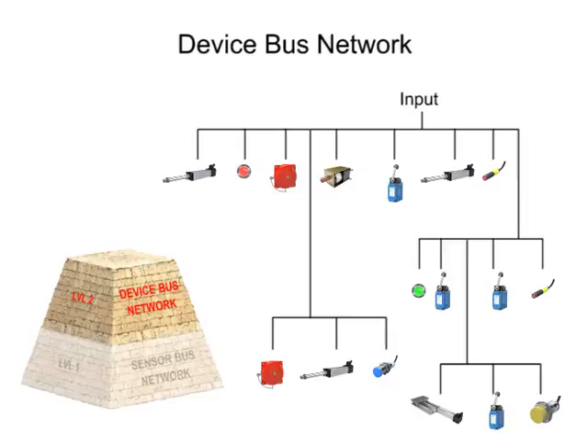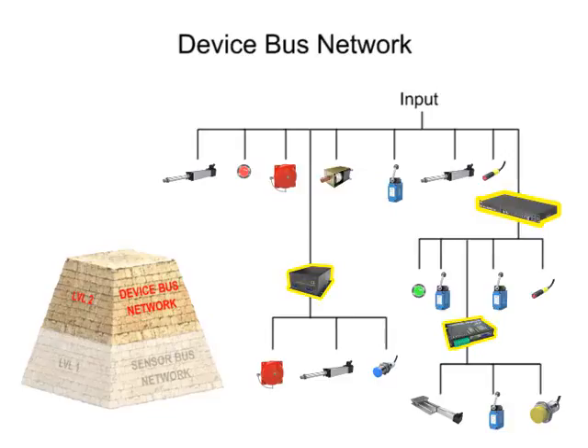The next increasingly complex level of industrial fieldbus networking is the devicebus network. The devicebus network is similar in function to the sensorbus network, but works on a larger scale, connecting many sensors and actuators together. The devicebus network also connects equipment to variable speed drives and motor control centers that allow for control of individual elements in the network.